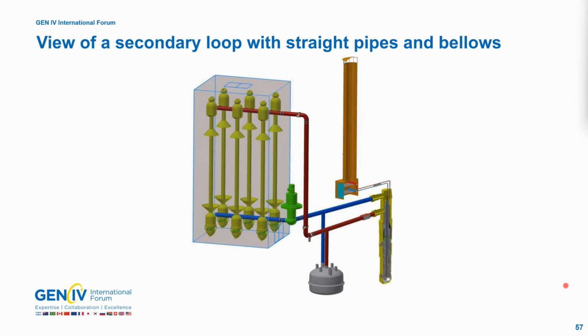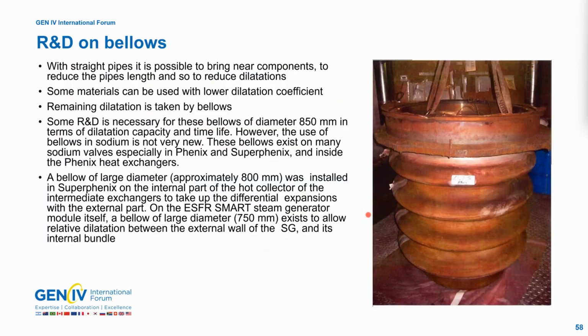Then we come back to the same view as before, with the view of the secondary loop with the straight pipes, and you see now the bellows. You need to have bellows. These bellows take the remaining dilatation on the pipes, but the dilatation is very reduced, because you can use materials with a low dilatation effect, and you can also have a very short length of pipes, 1 or 2 meters, and so these bellows have not a lot of dilatation to take into account. Thanks. Next slide, please.